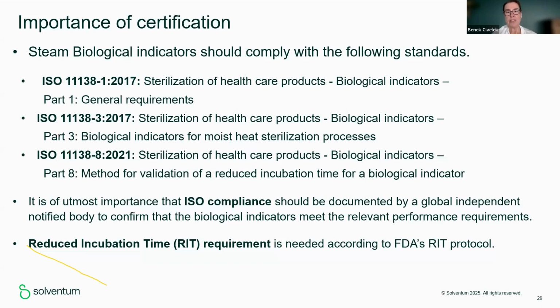There is an important point about choosing an indicator. There are several standards, but the indicator you are choosing should also be able to provide you some certification, really showing that they are complying with the standards. For steam biological indicators, there are three important standards. The first is ISO 11138-1. This is the general approach for biological indicators, the general concept. When we talk about -3, this is telling more about steam biological indicators, the spore and the number of population.